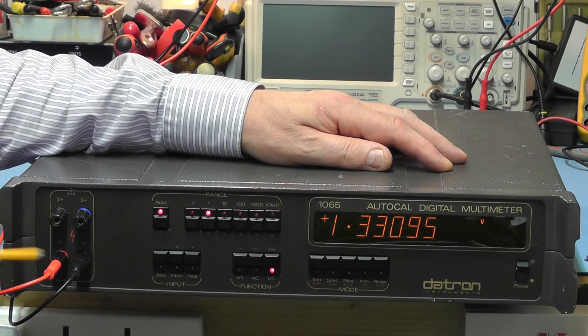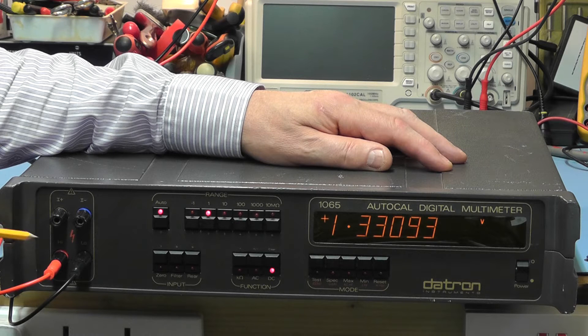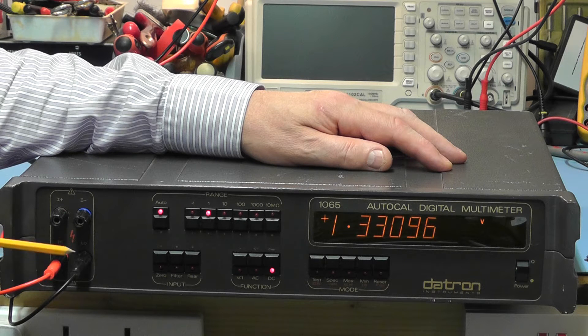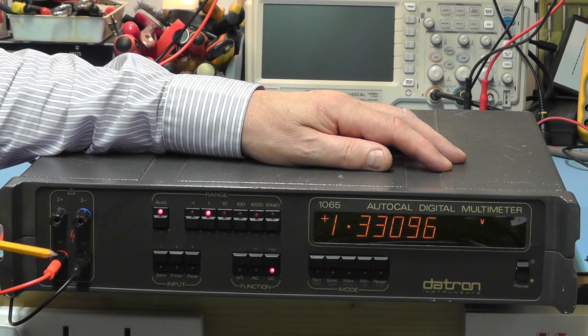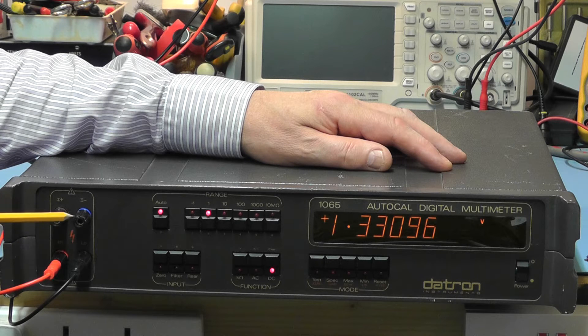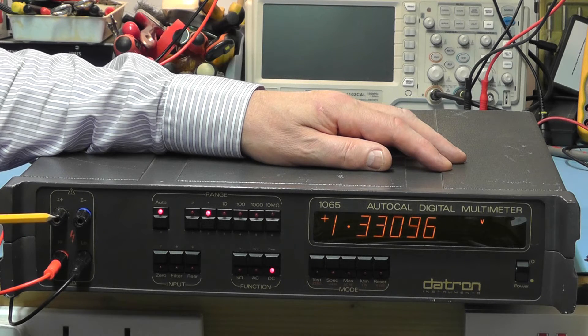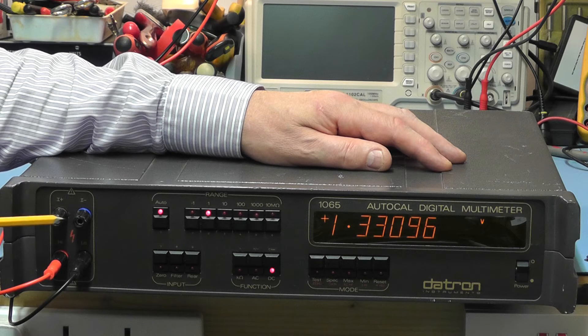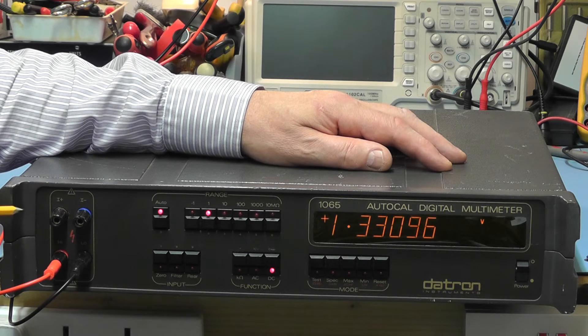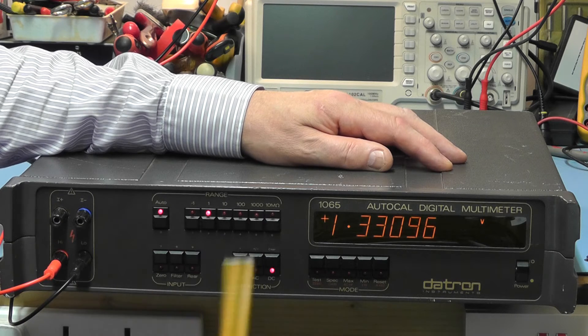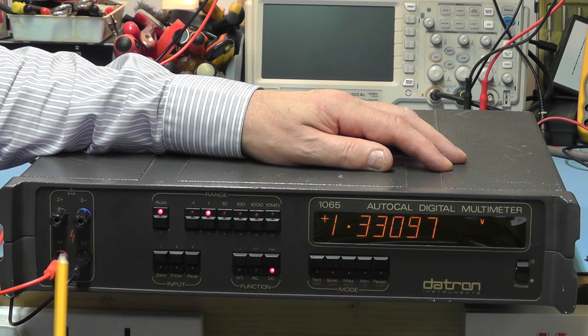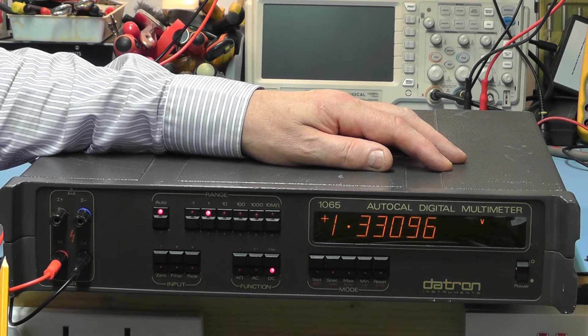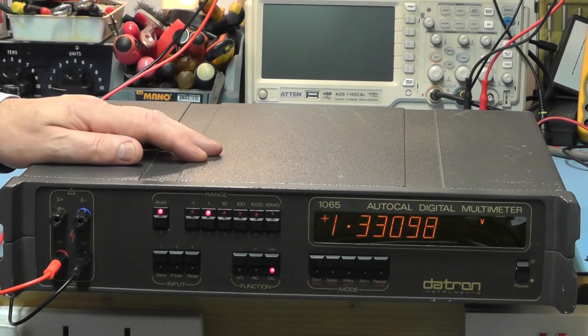At the left here we have the four input connections. The bottom two are the main two, the plus and the minus input connections, and the other two are used when you're using a four-wire lead such as a four-wire resistance reading function. So they're the main controls on the front panel. Let's have a look at the rear of the unit.